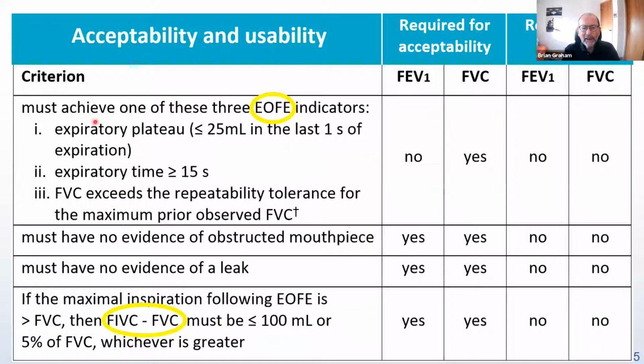One of the other things, of course, is that we've got 3 different indicators now for end of forced expiration, and you must achieve one of them. That's not a requirement for FEV1, because again, as long as the first second's okay, you can measure an FEV1. But to get to an acceptable FVC, you need to be hitting one of these indicators.